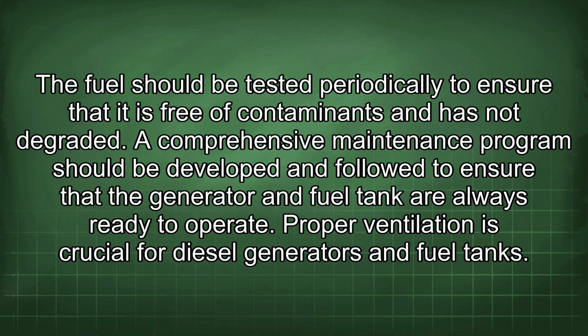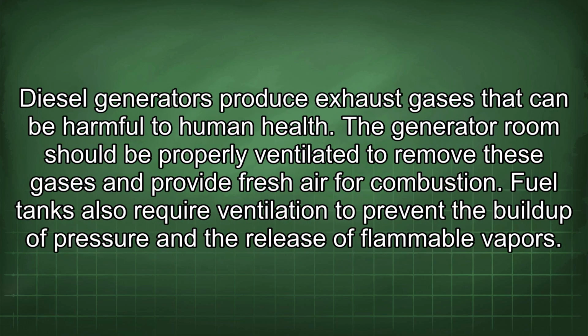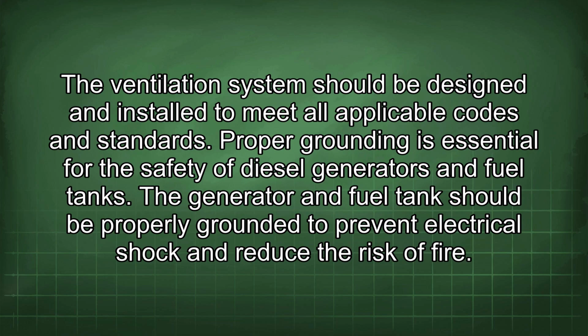Proper ventilation is crucial for diesel generators and fuel tanks. Diesel generators produce exhaust gases that can be harmful to human health. The generator room should be properly ventilated to remove these gases and provide fresh air for combustion. Fuel tanks also require ventilation to prevent the buildup of pressure and the release of flammable vapors. The ventilation system should be designed and installed to meet all applicable codes and standards.